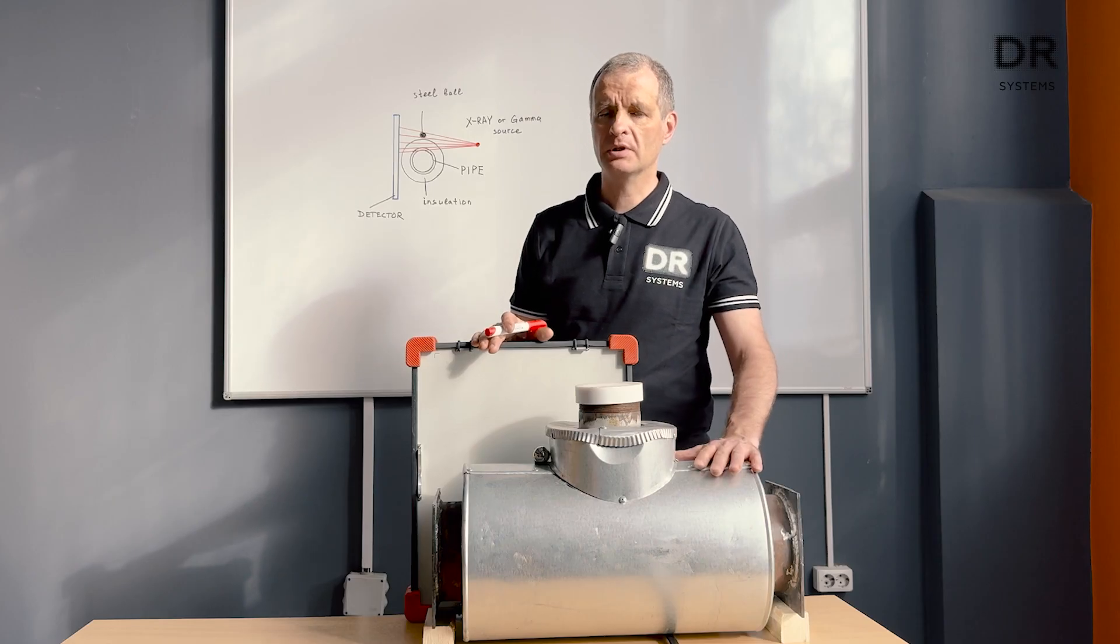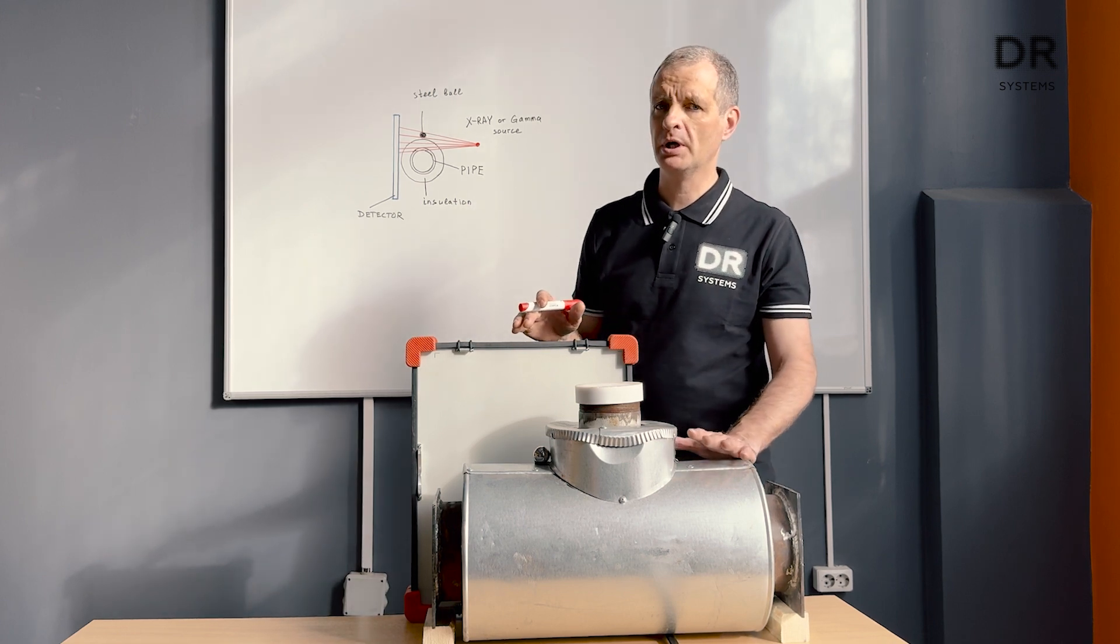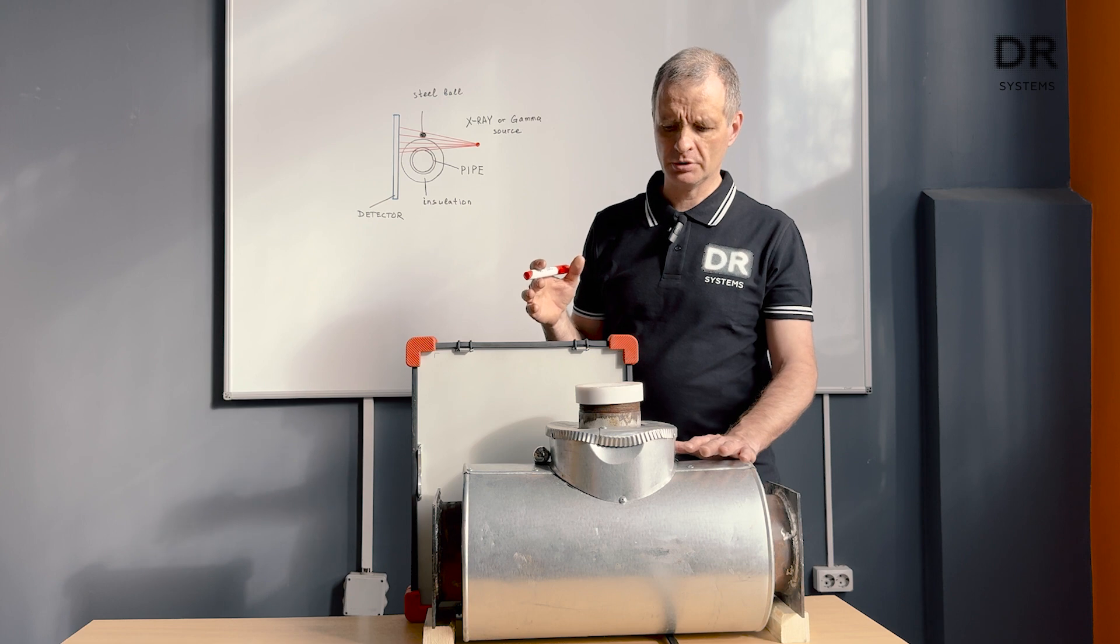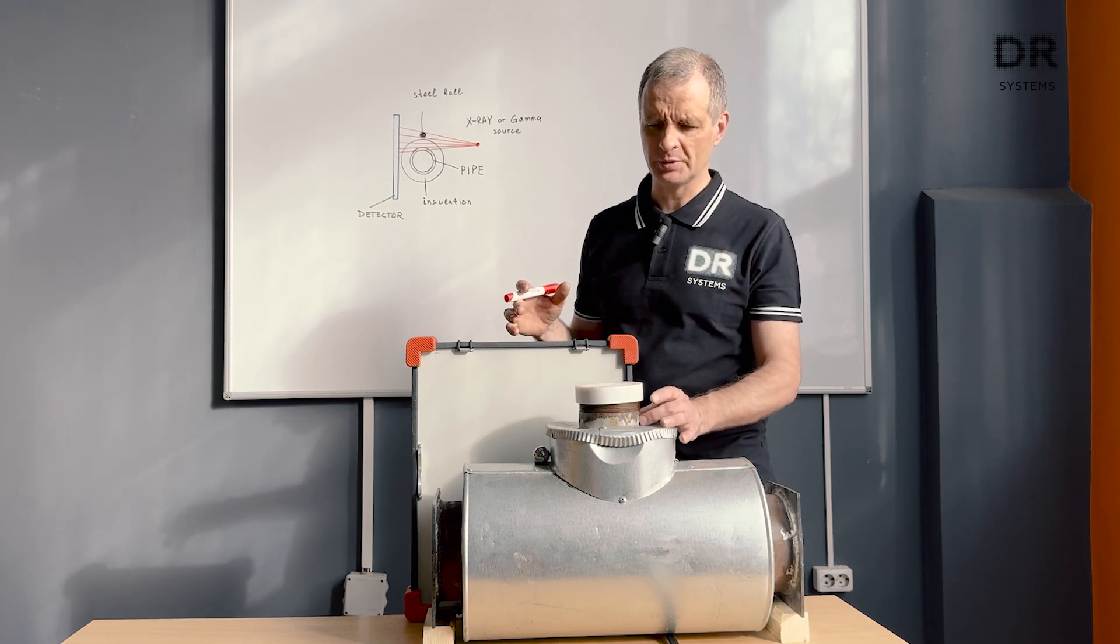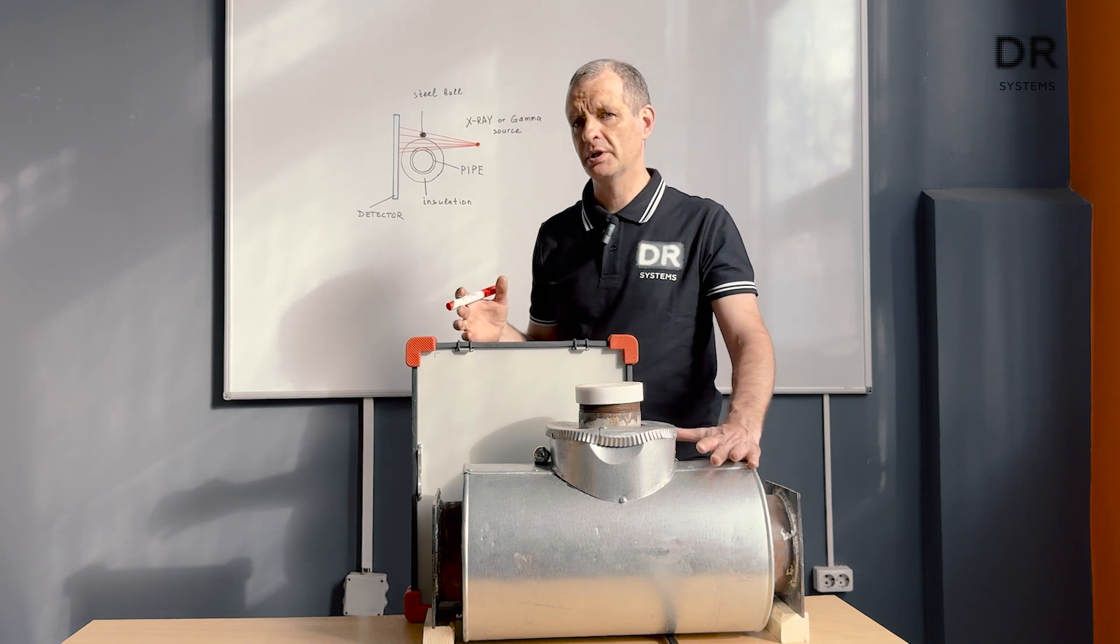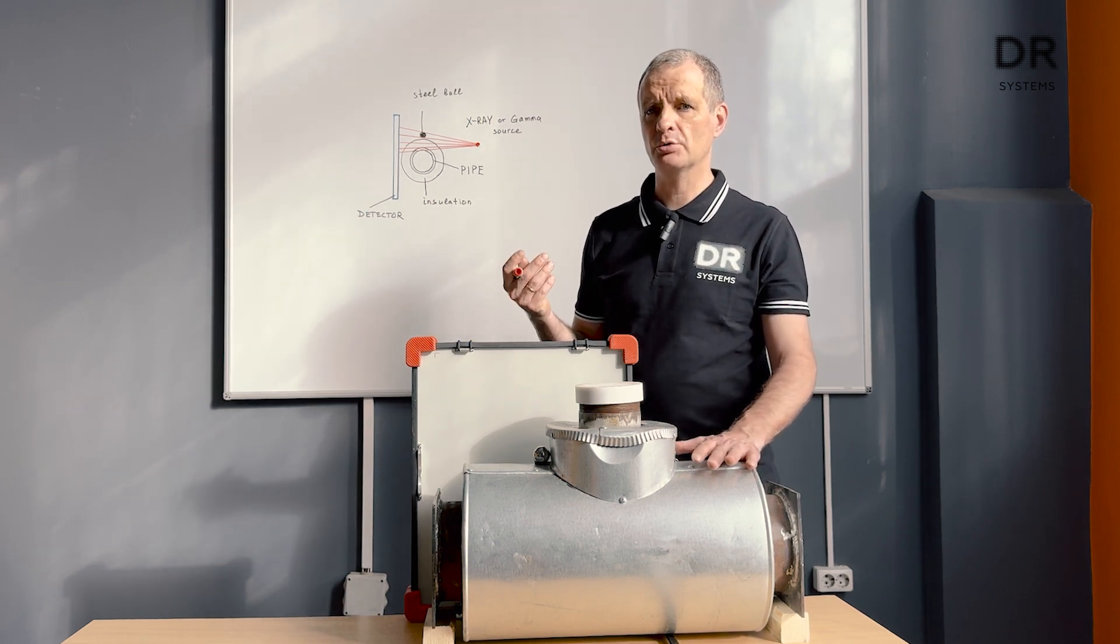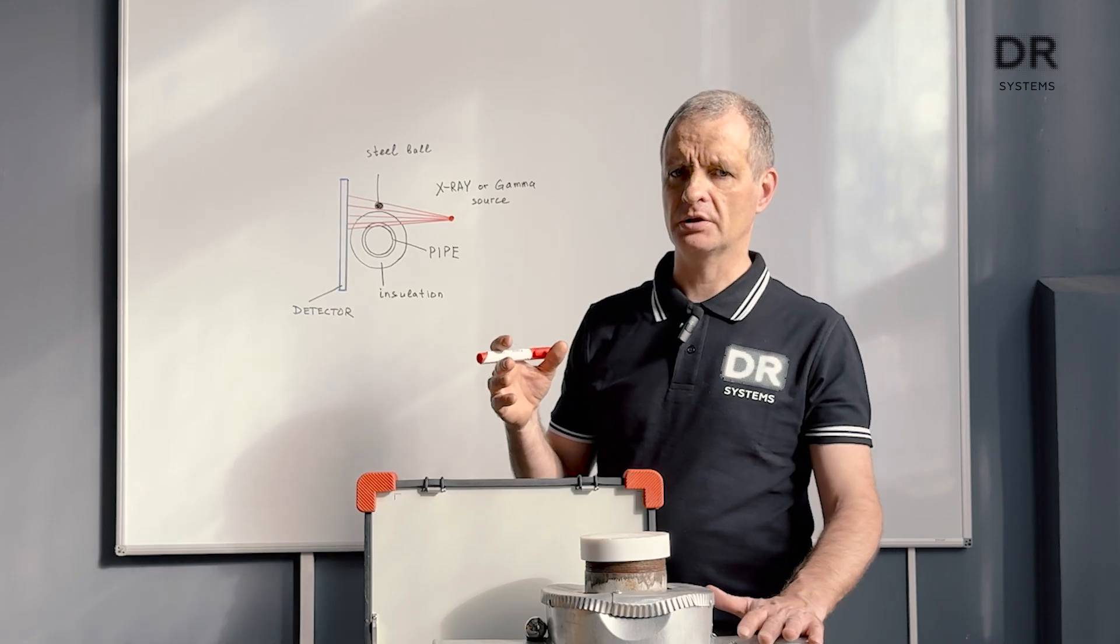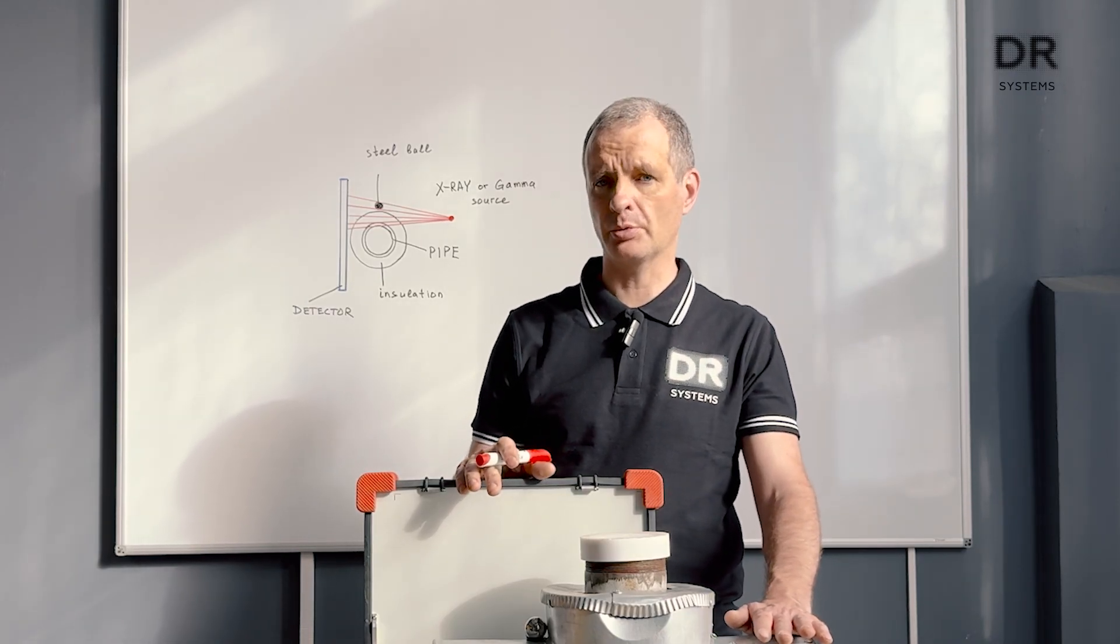Here's the pipe covered by heat insulation, as most of the pipes at oil refineries are, and we want to know what is the wall thickness of this pipe. As soon as the pipe is covered by heat insulation there is no access and we cannot use ultrasonic sensor to measure it, and digital radiography gives us an opportunity to do that.